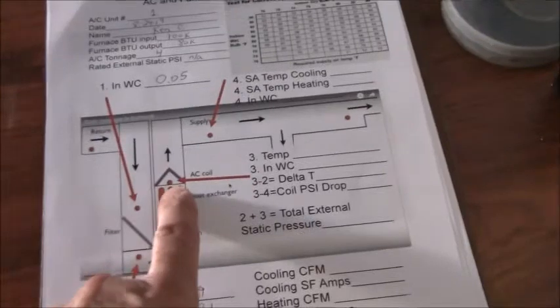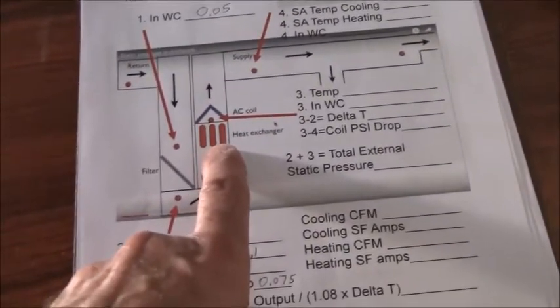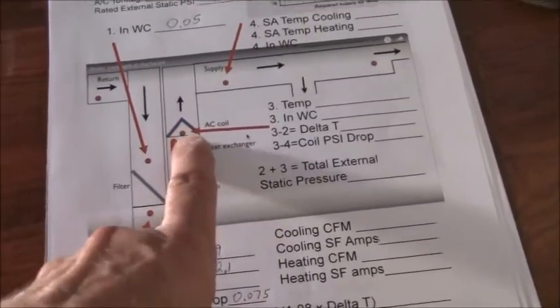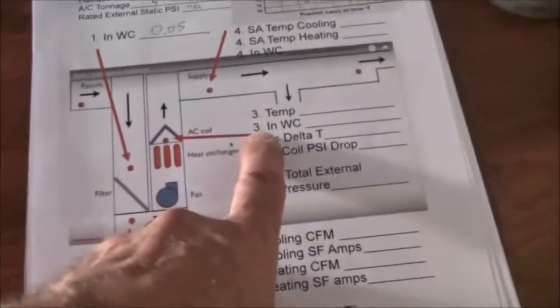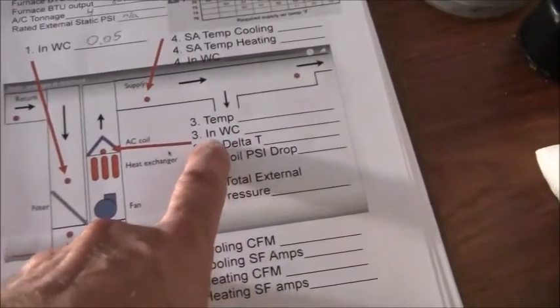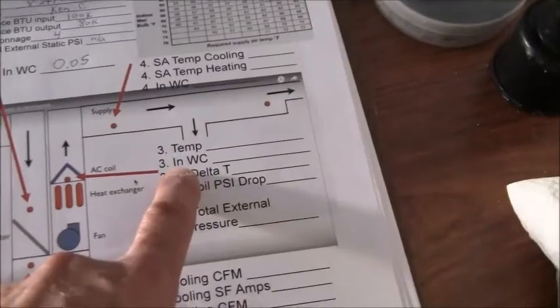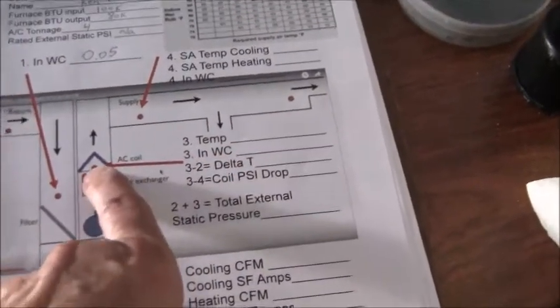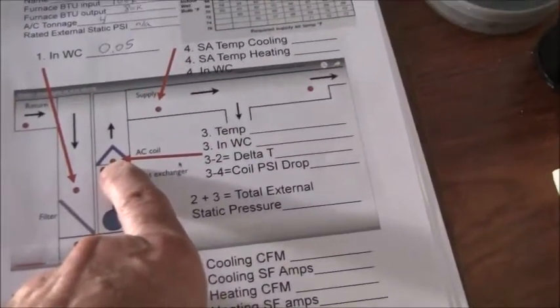Now, we want to get the reading after the filter and before the coil, the heat exchanger. That's going to be point number 3. I want to know what that is in inches of water column. Now that is going to be a high pressure, not a low pressure.